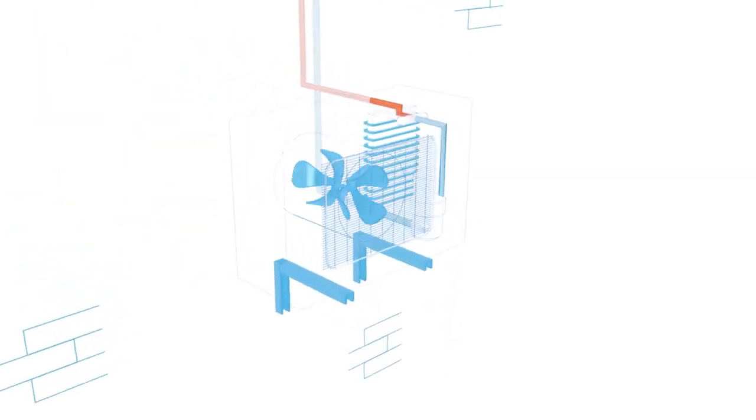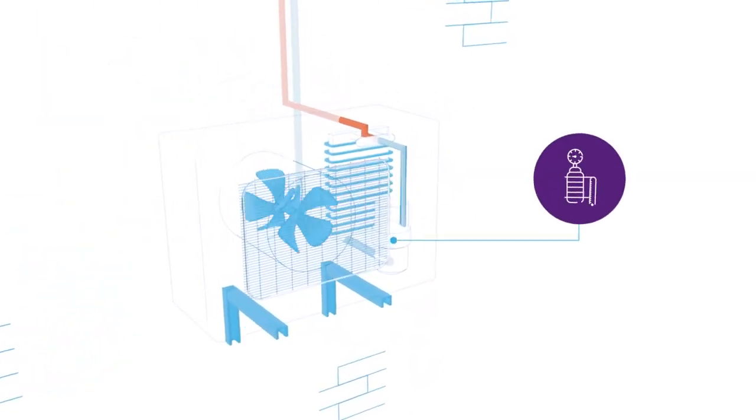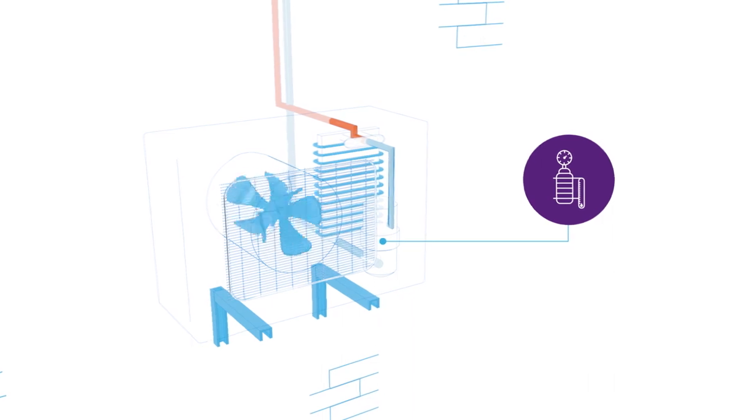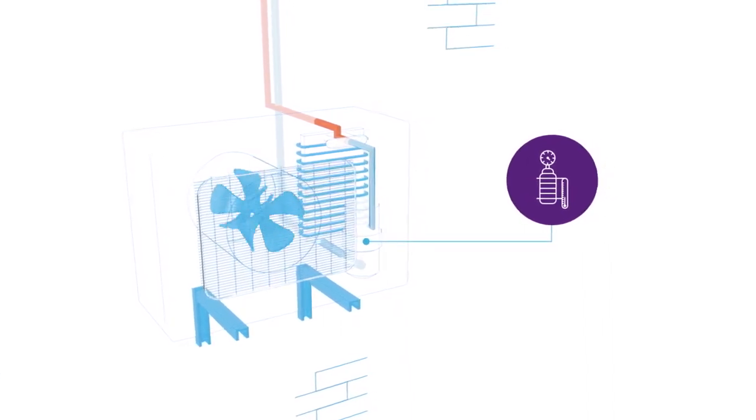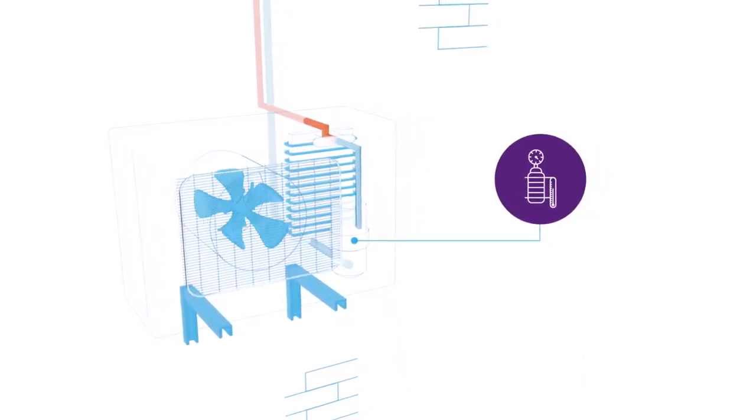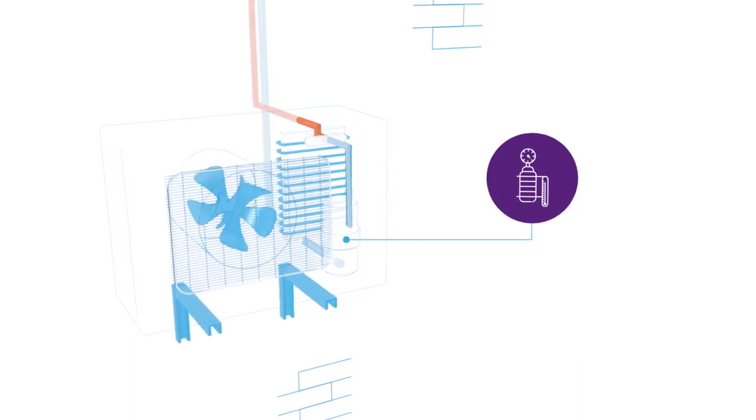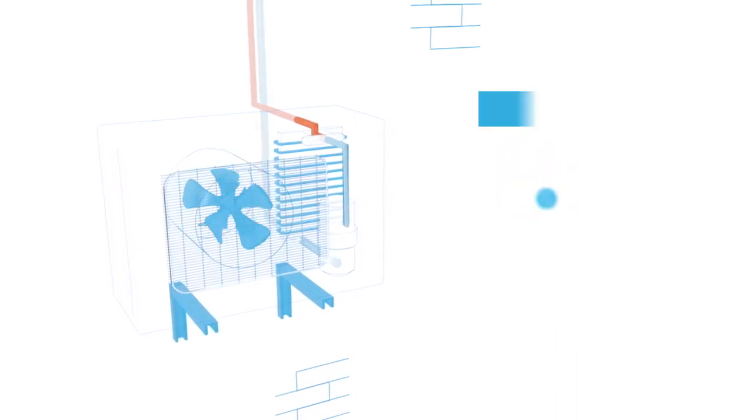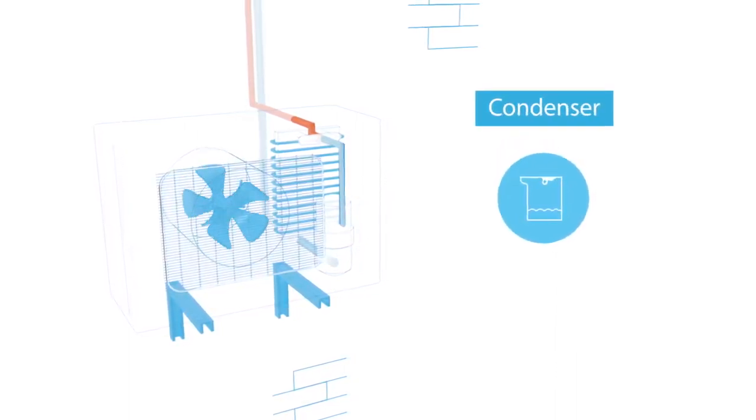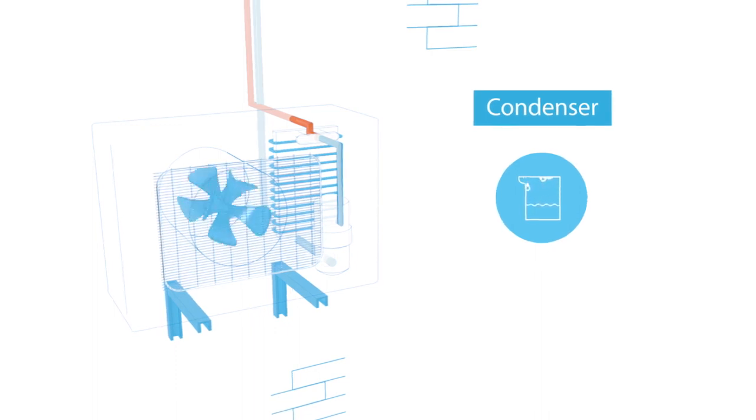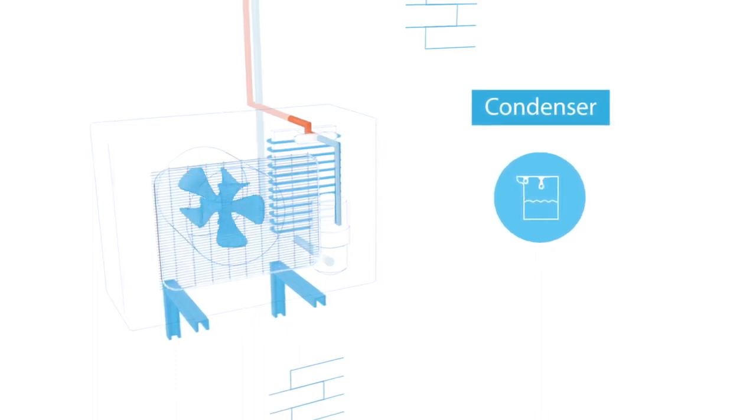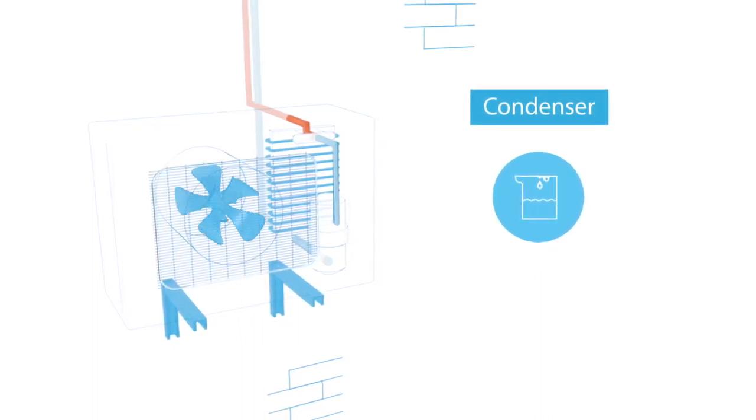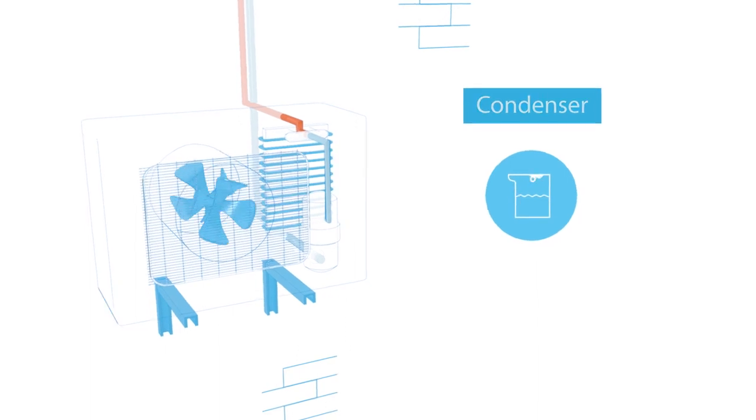The compressor is based in the outdoor unit. It compresses the gas which heats up due to the compression and at the same time increases the boiling temperature. The heated gas is cooled down in the condenser, which is also located in the outdoor unit. The hot gas releases its temperature to the outside air and turns into a liquid.